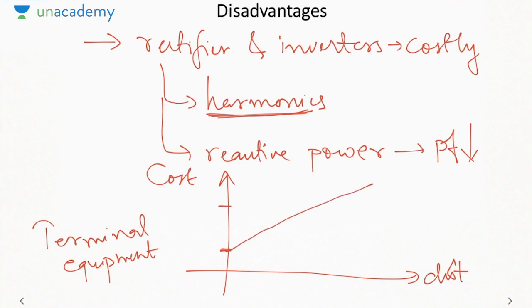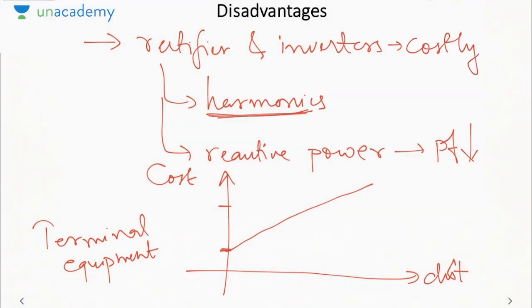But AC has more conductors, like in 3-phase 3-wire we need 3 conductors. So its cost will increase at a higher rate with distance as compared to DC, because DC will need at the most 2 conductors. So its slope will be less. At this point both costs are equal. It is called the break-even distance, where both costs are equal. At a distance higher than this, HVDC is preferable. At a distance lower than this, we use HVAC. That is how we plot this sort of curve to decide whether to go for HVDC transmission or stick to HVAC transmission.